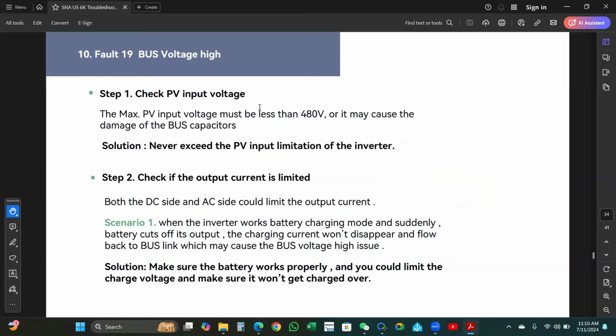Step 1, check PV input voltage. The max PV input voltage must be less than 480 volts, or it may cause damage to the bus capacitor. Solution: never exceed the PV input limitation of the inverter, which is 480 volts.